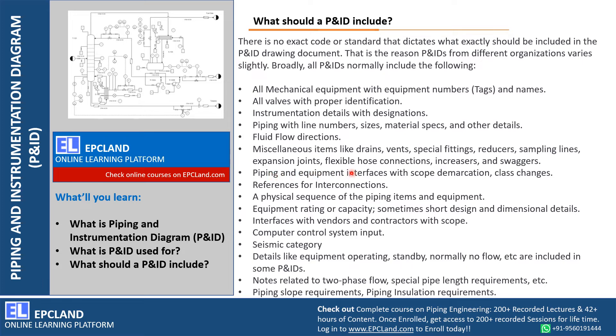Piping and equipment interfaces are shown — what kind of nozzles are there, their rating and size — and demarcation is done for these interfaces. References for interconnections are provided, so if something is not detailed in a particular P&ID, a specific reference is given to obtain those details. The physical sequence of piping items is the most important part — how items are connected, how flow moves from one point to another, how they are associated with other equipment. Equipment rating and capacity, and sometimes short design and dimensional details, are also mentioned.